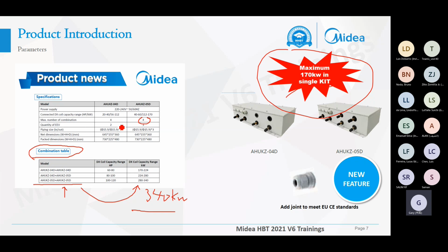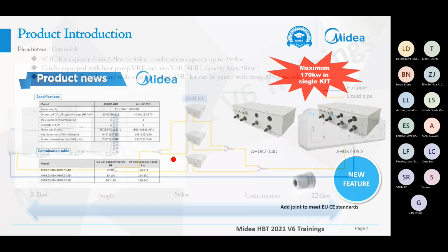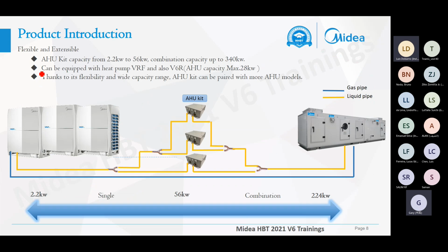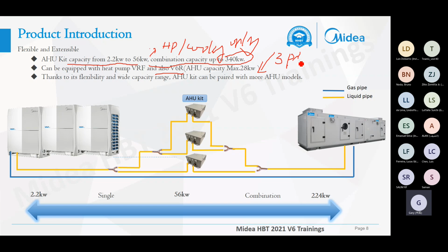But normally we can use the master for larger numbers of combinations, with flexible and extensible functions. The AHU kit capacity can range from 2.2 kilowatt to 56 kilowatt for a single kit, and for combinations, the capacity can go up to 340 kilowatt. Just as mentioned before, this combination ratio is for heat pump VRF or cooling only systems. And for the 3-pipe VRF systems, we can only allow AHU capacity and maximum mount up to 28 kilowatt. This one is very important.